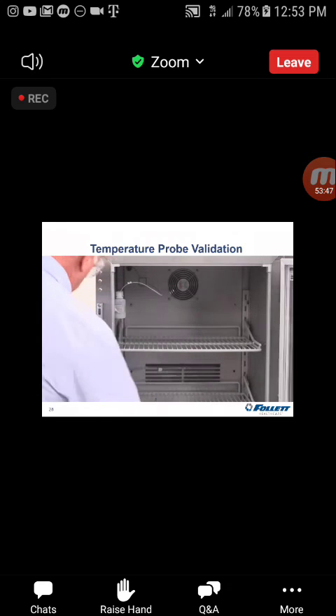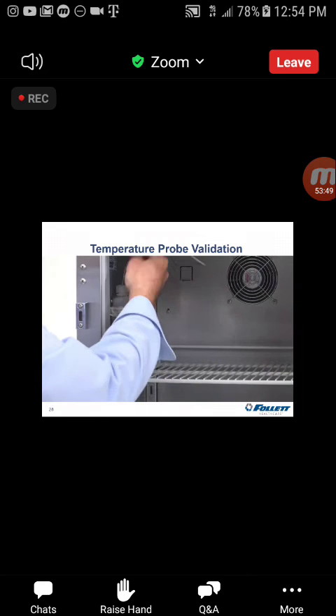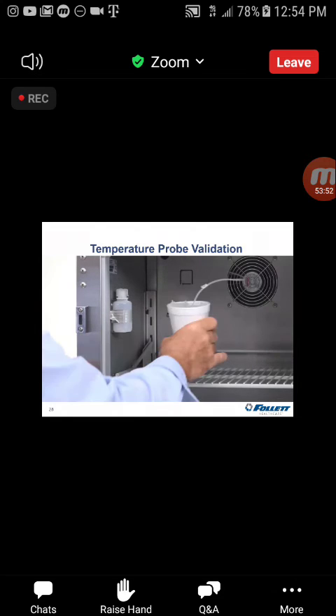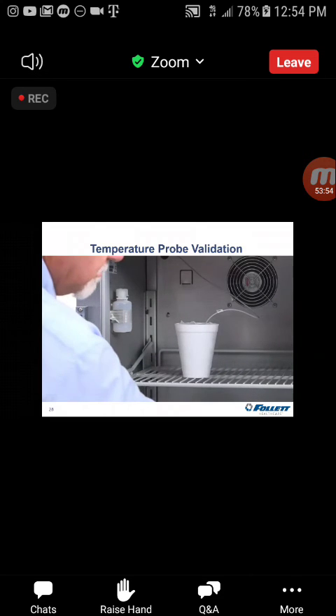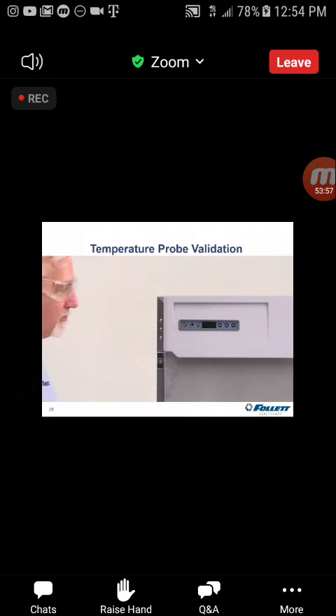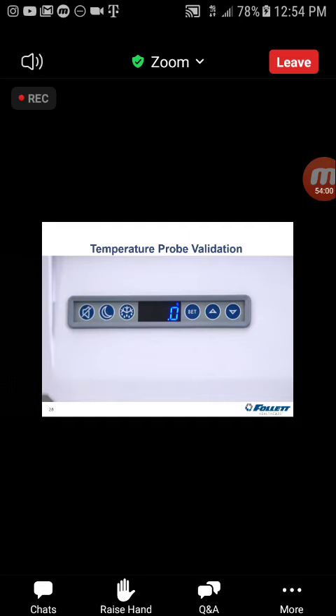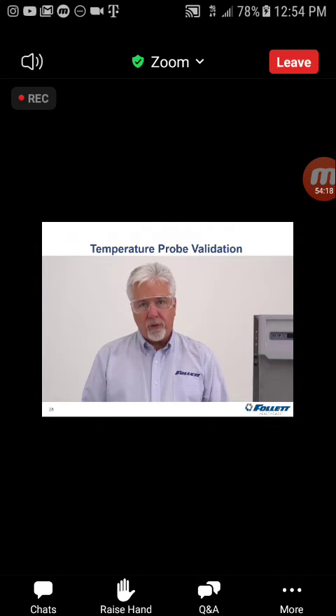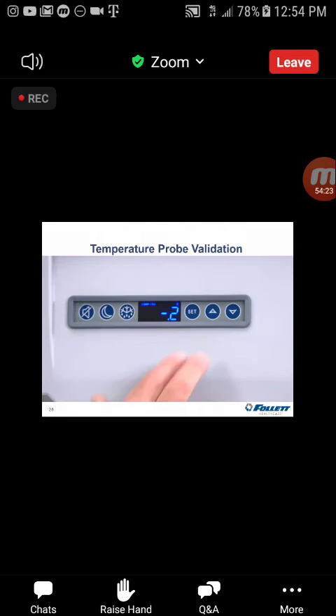To validate the probe, we are going to insert it into the ice water bath. In this case, we're using the P3 probe. Sufficient time should be given to allow the probe temperature to stabilize in the ice water bath. Once it is stabilized, it should read 0 degrees C. The specification tolerance on the probe is plus or minus 1 degree C. As long as the probe is within that range, the probe can continue to be used. If the probe is out of that range, the probe should be replaced. Then, as long as it's close, we can certainly adjust for that by going into the offset function.